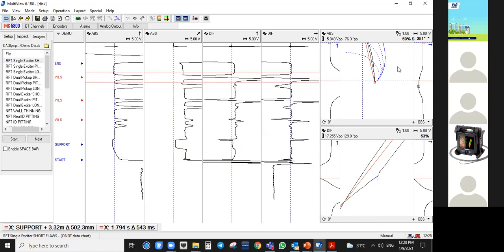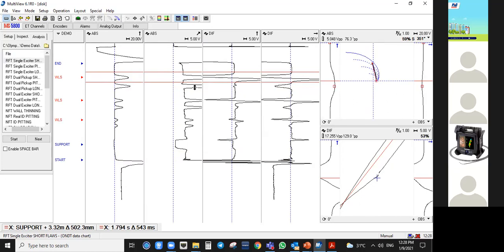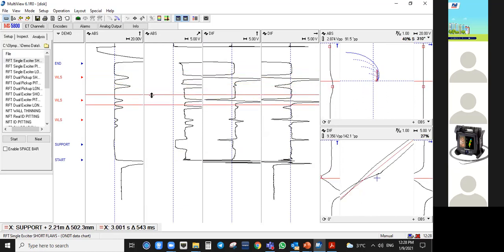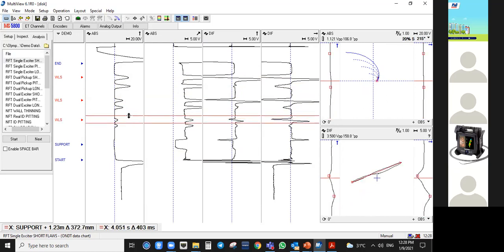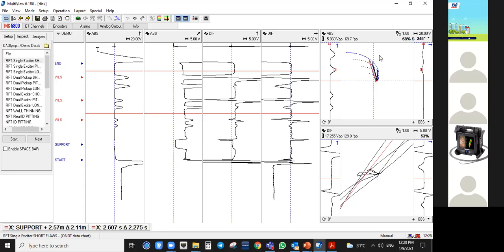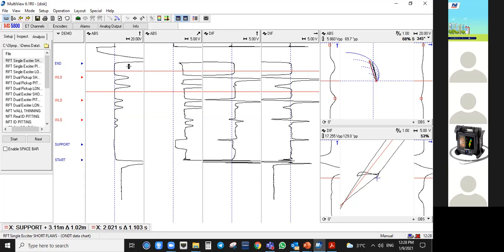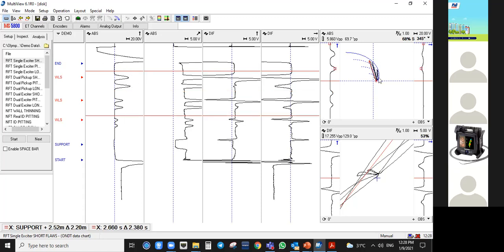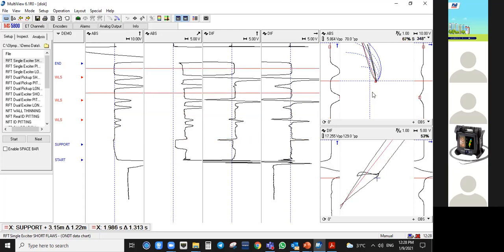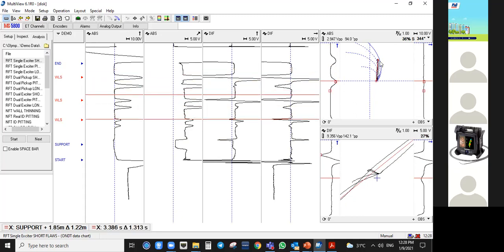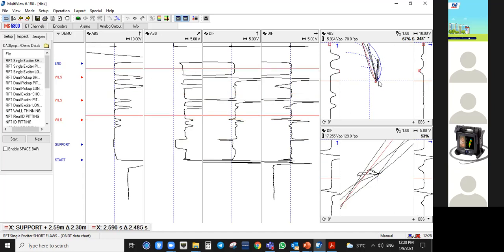Let's go here. This one is 40%. This one is 60. Usually what we do is we look first like this. Before calibration, we first scan the tube and must see what the difference is between two defects. So you see here, this side is for 60% wall loss and this side is 40% wall loss. When you combine these two, you have a V shape, right?